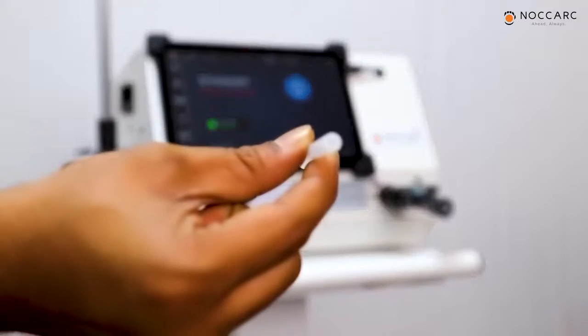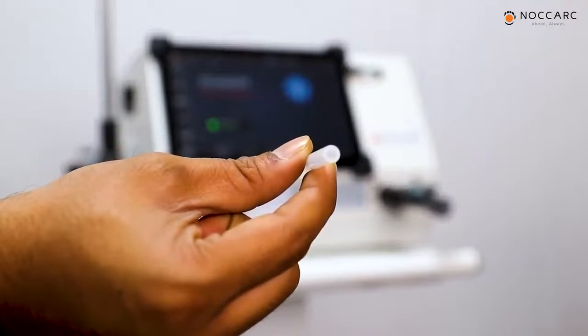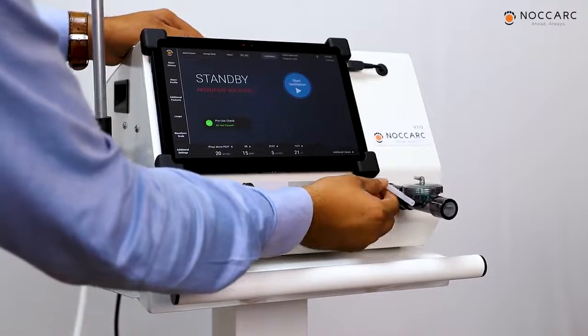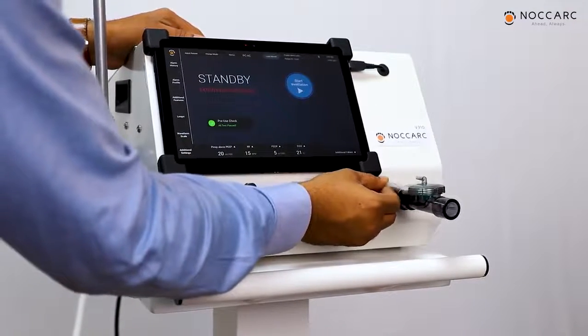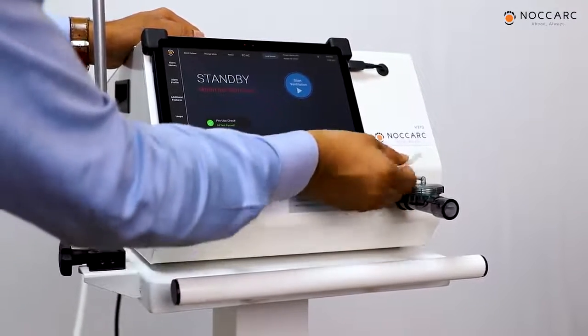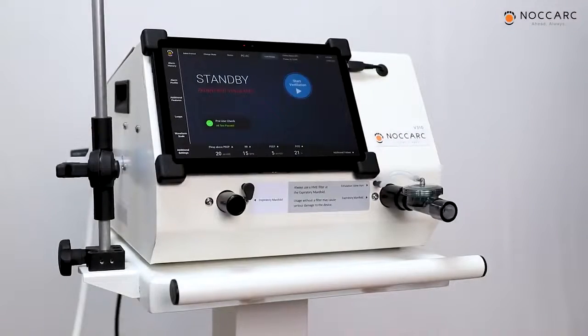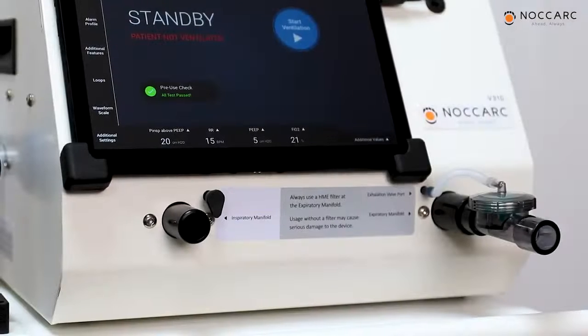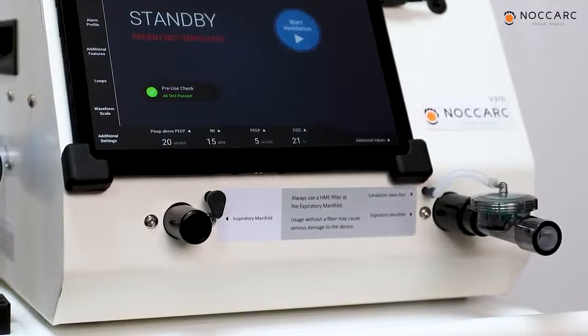Connect silicone tube provided with standard kit between exhalation valve port and active exhalation valve. Active exhalation valve is used to maintain patient's PEEP, that is positive end expiratory pressure. The active exhalation valve connected with V310 is a reusable one. Users can use this active exhalation valve on multiple patients after doing autoclave every time.